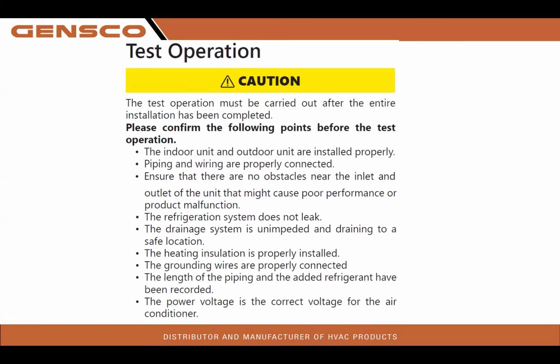Test operation. To test operation, all we really need to do is make sure that all of our system checks are done. We did do a pressure test. We did pull a nice tight vacuum. We did dump the charge. We did add for additional line set length. Our power is correct. Our power is correct in the indoor. Our thermostat's lit up. And now we're just going to go ahead and give it a call for cooling.